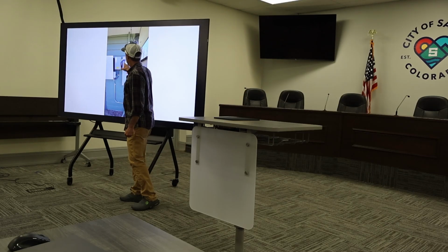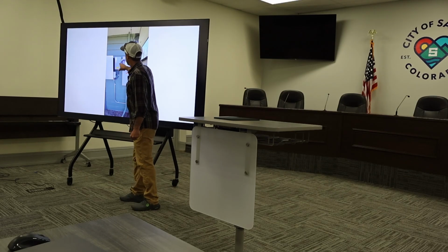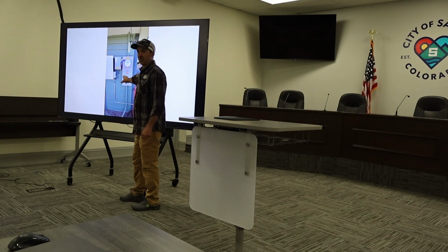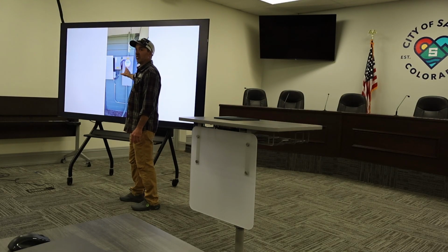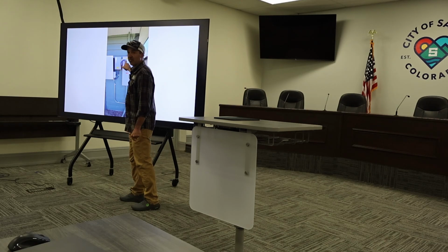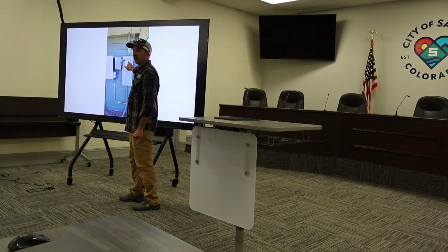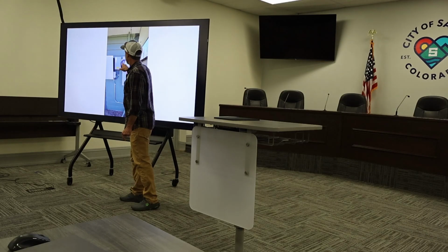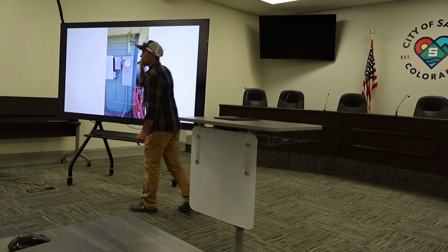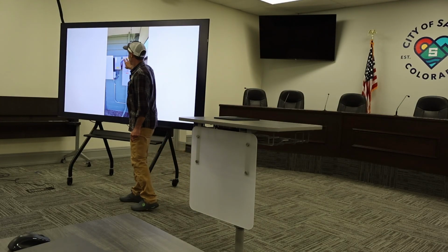In this particular case, I'll go to the next slide. I wish there were more electricians here because this is always a debate. This is a way to interconnect the system where you don't have to worry about the bus rating of the panel, the 120% rule. It avoids all that since you can use 100% of the panel rating. So it's kind of a retrofit feature, pretty nice, feeding from the solar back into the grid through that meter collar.